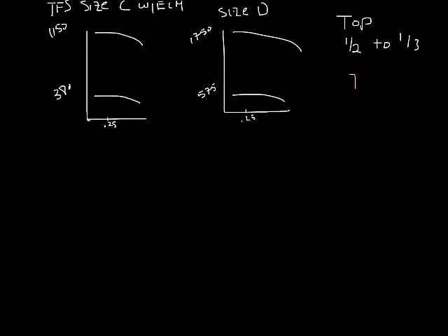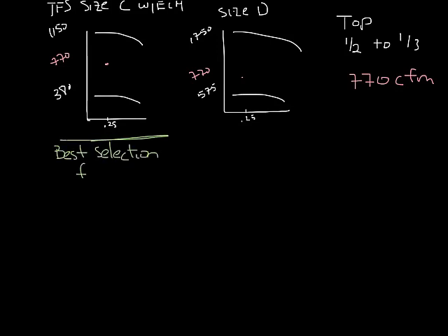So for our example, if you need 770 CFM to match the primary airflow, because this is a series fan box, you would want to select the size C TFS, because it's about halfway up in the airflow range, whereas in the D it's near the bottom of the curve. So you would select a TFS-C with an 8-inch inlet, which is what we would call a CO8.